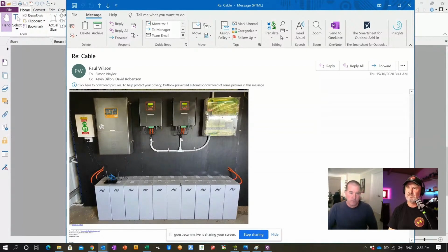So this 44 kilowatt hour battery can charge in about 2 and a bit hours from empty to full. And if we start a generator up and run it through the SP Pro, say a 15 kilowatt AC generator, we could charge 15 kilowatts DC onto this bank, along with the PV of 20 kilowatts, which is 35 kilowatts of power, which would charge a 44 kilowatt hour bank in about an hour and 10 minutes or so. So that's a very simple, elegant system with a lot of power and a lot of simplicity. And in this case, indeed, yeah, it's just very simple to install.